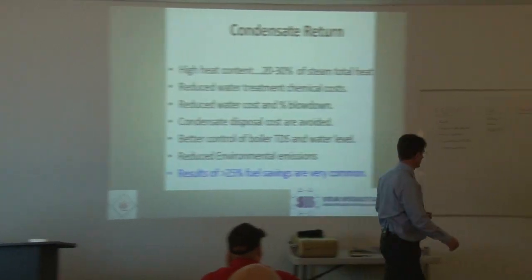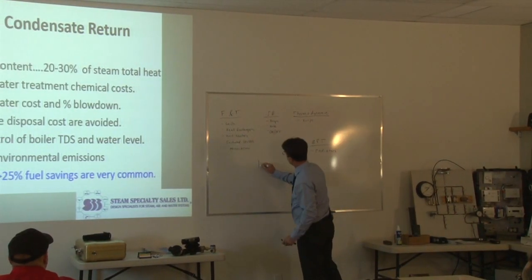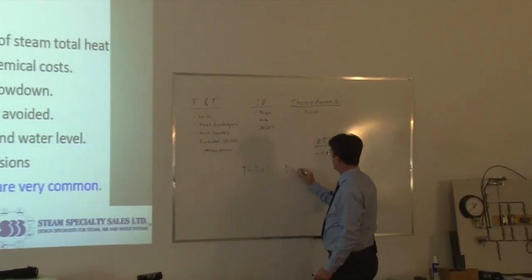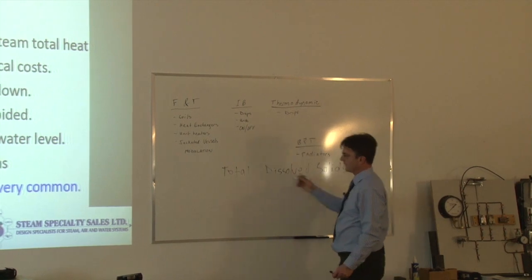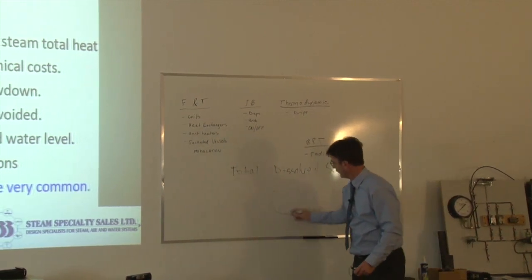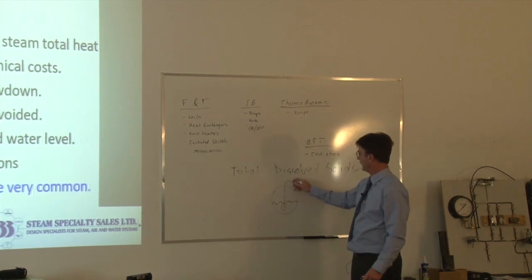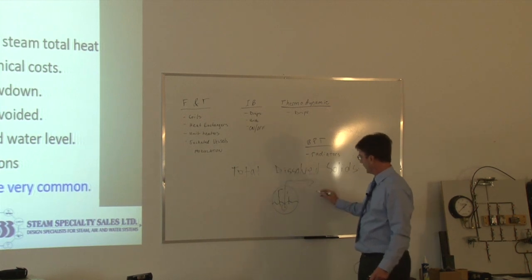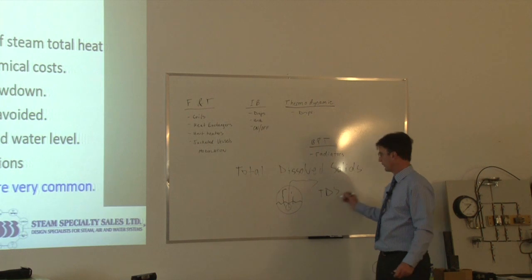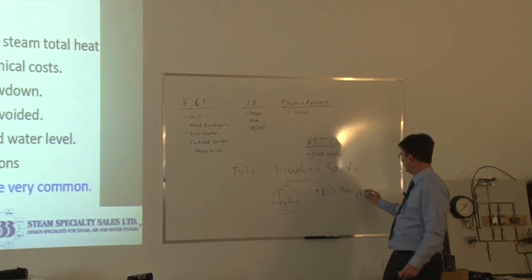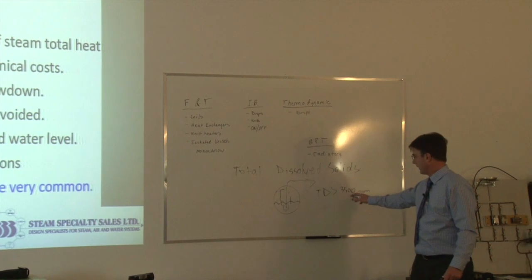TDS stands for total dissolved solids - solids in suspension inside the water. Inside a boiler, water is heated up and turns to steam, goes out into our system. The heavier particles fall back down. Most boilers have an acceptable level of TDS - many smaller boilers accept around 3,500 parts per million. Too high a TDS rate causes priming, carryover, and poor heat transfer. But too low means you'd be blowing down the boiler constantly, causing energy losses.